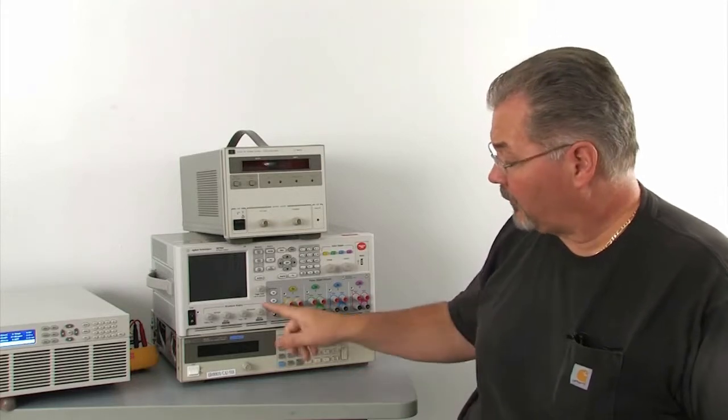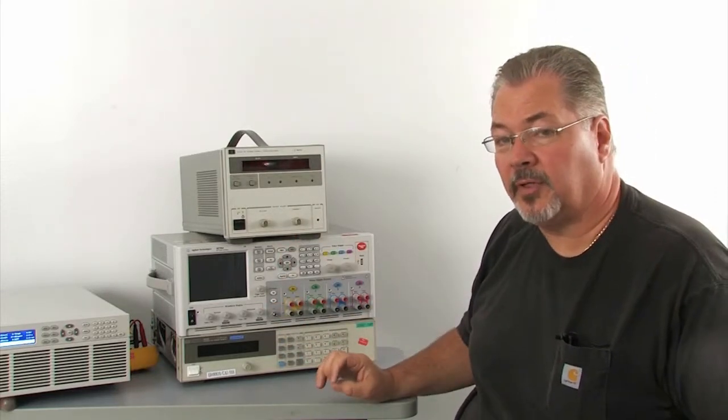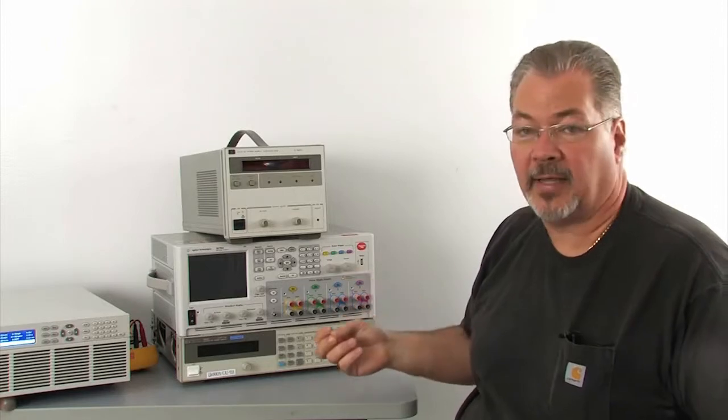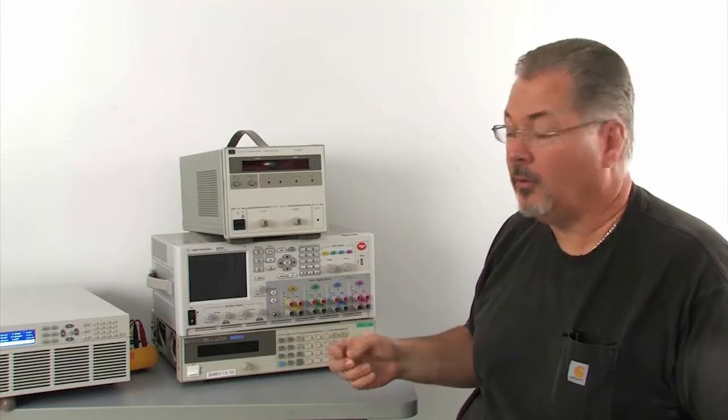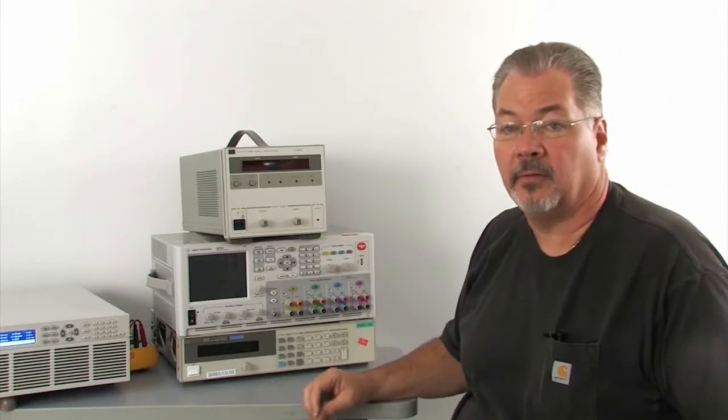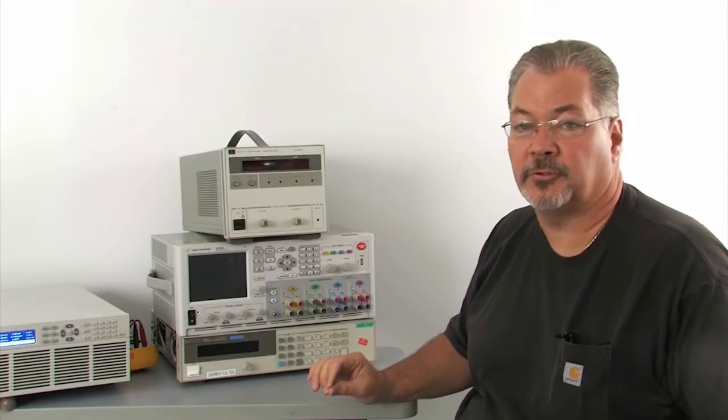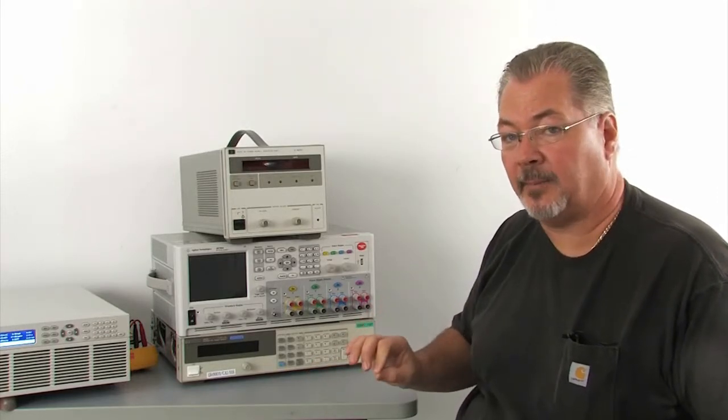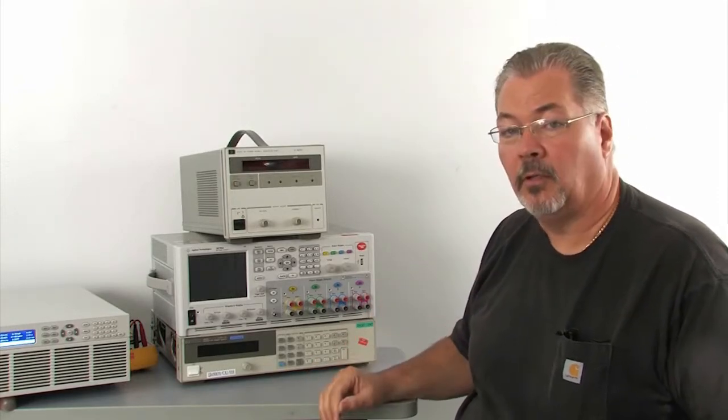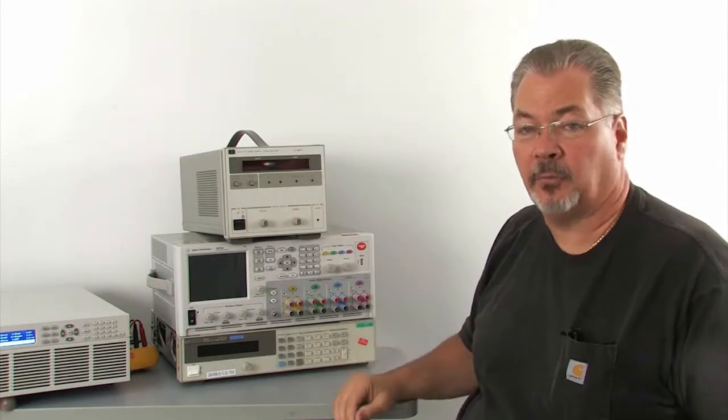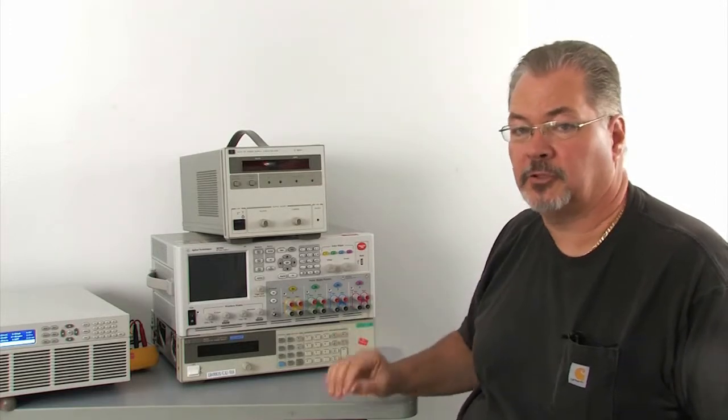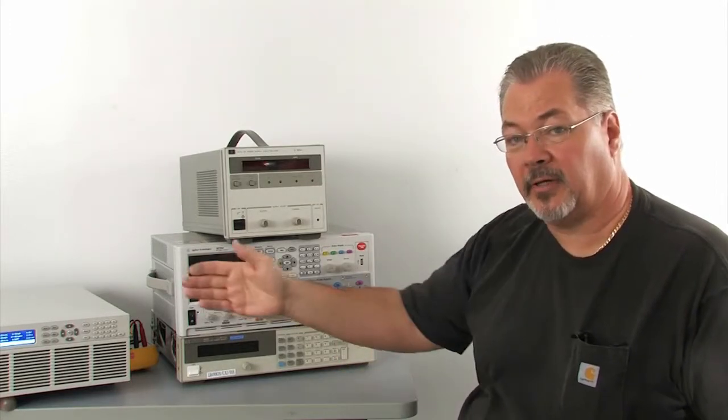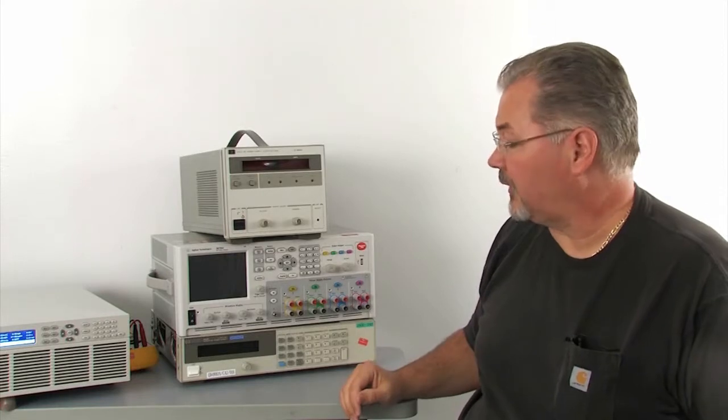Both of these boxes can have trouble with the inrush limiting resistor. Either the wrong value has been put in, or they could have forgotten to put the resistor in, or the resistor could be internally damaged and not functioning at all. So the unit would still turn on but would have a huge inrush current, which you would be able to catch with our AC source in production testing.